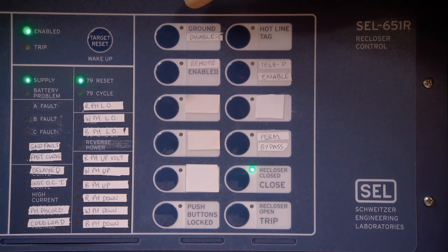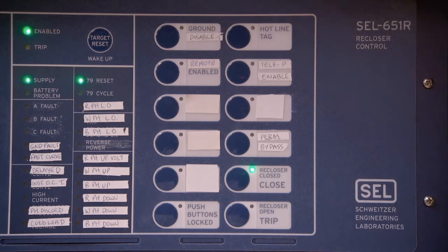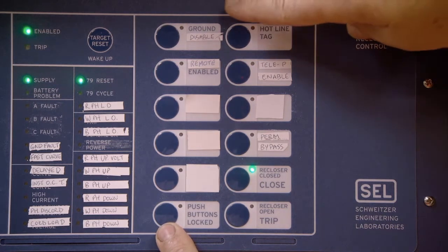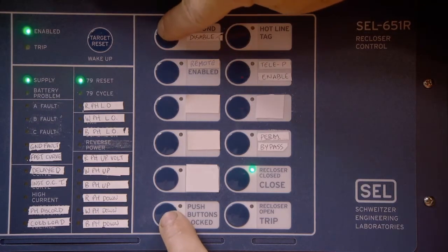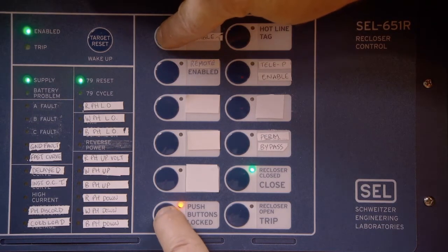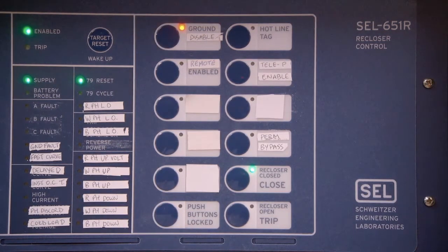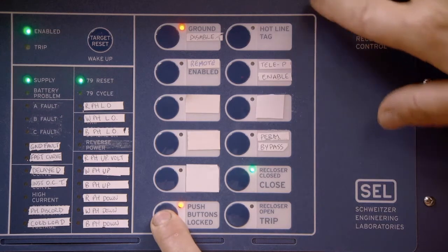Ground disable. This is typically used in switching operations or testing procedures. This is a 2-button operation. Press both the push buttons locked and ground disabled buttons simultaneously. The ground disabled indicator will turn yellow. Repeat this operation to reapply the ground.